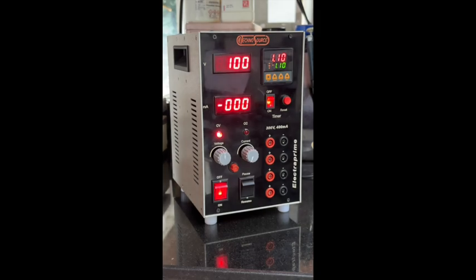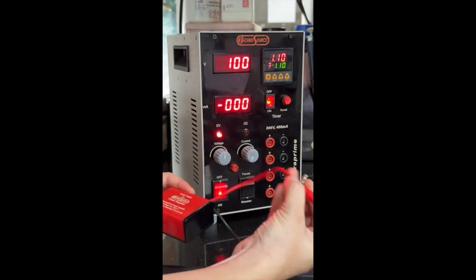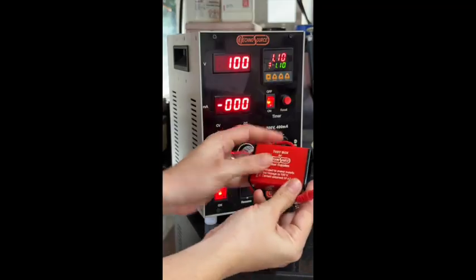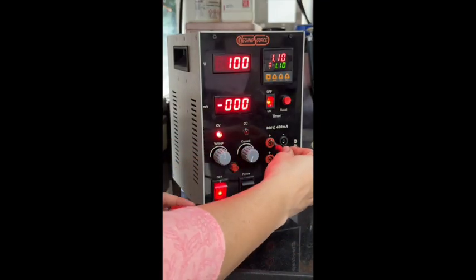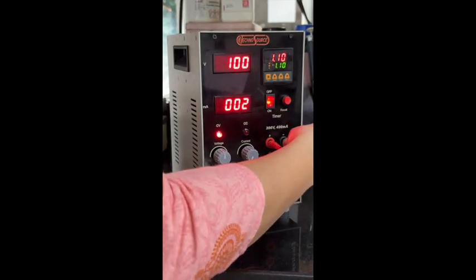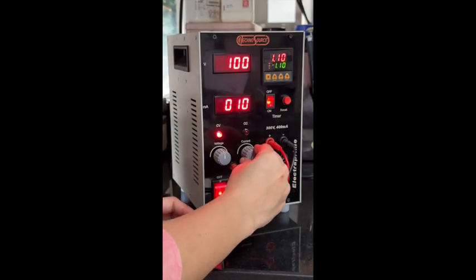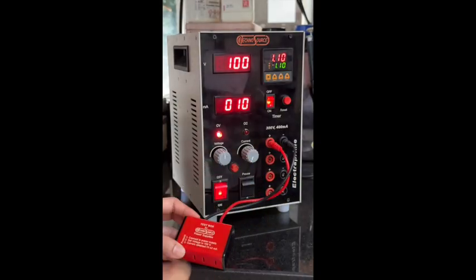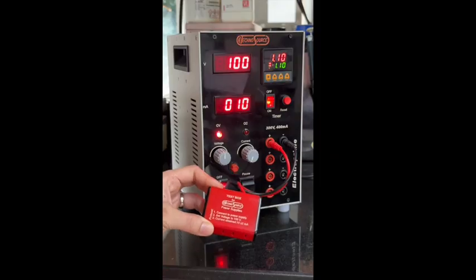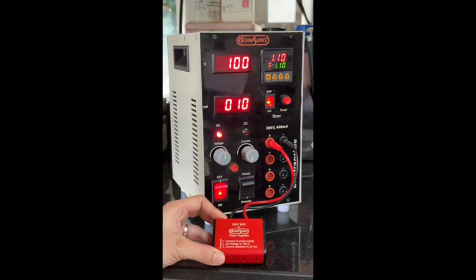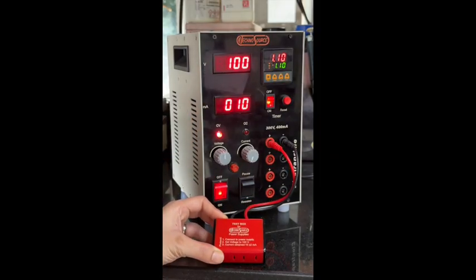That is, no apparatus is connected. Connect a test box or connect any apparatus with the appropriate buffer. Turn the current knob fully clockwise. If using the test box, follow instructions on the box. Or if you're using an apparatus, then set the voltage using the voltage knob to the desired value.